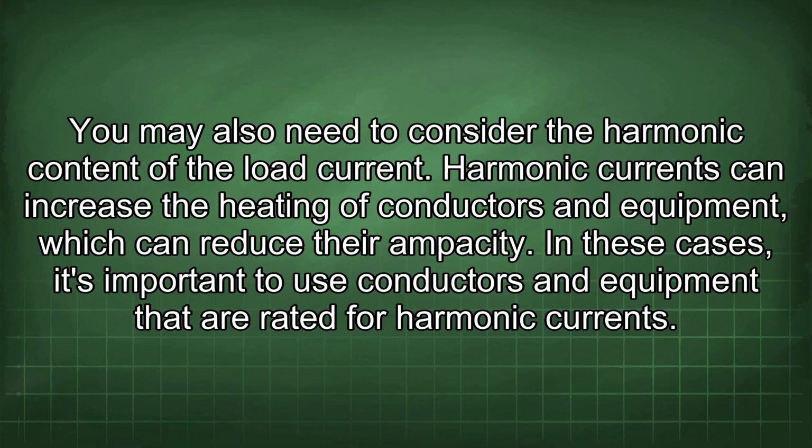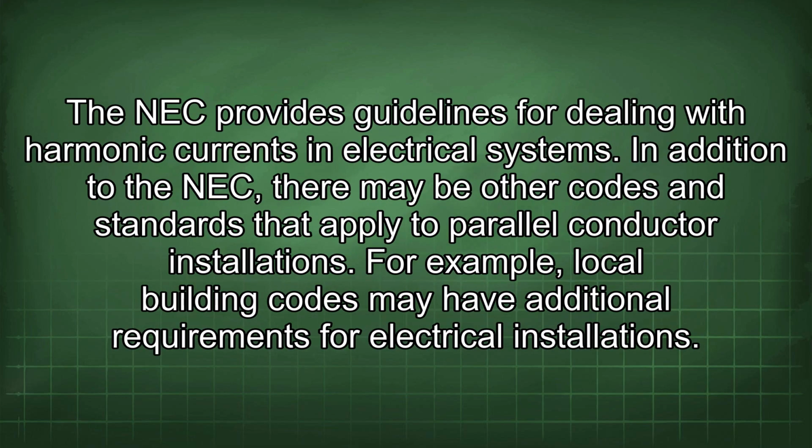You may also need to consider the harmonic content of the load current. Harmonic currents can increase the heating of conductors and equipment, which can reduce their ampacity. In these cases, it's important to use conductors and equipment that are rated for harmonic currents. The NEC provides guidelines for dealing with harmonic currents in electrical systems.